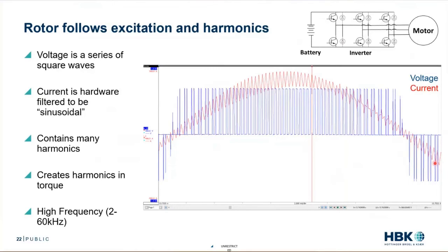This tells us a couple of things. One, using discrete switches we can power this motor. Two, this current wave is going to have a lot of harmonics, which means harmonics in the magnetics — a magnet that looks like that spiky sine wave. That magnet equals torque, so we'll have a torque with torsional vibration caused by the inverter. Any harmonics in the stator or current get transferred to that shaft. This inverter example has a particularly low switching frequency with high harmonic amplitude, but it's going to exist in all systems. Switching frequency typically ranges from 2 kHz to 60 kHz depending on the application.